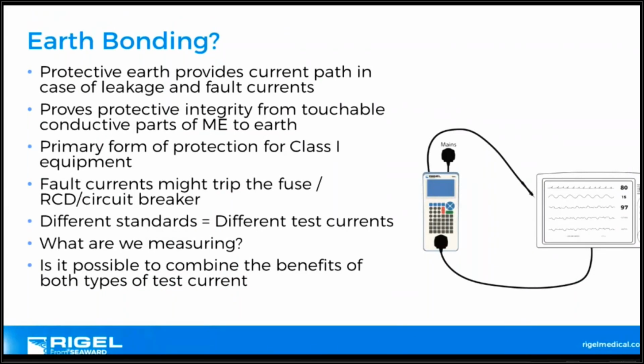So, as people would probably say, when we do earth bonding, protective earth is giving us that protective integrity from touchable parts. We've stressed that if the conductive part was to become live or hazardous, it's given us the primary form of protection for class 1 equipment. Then hopefully it will trip the fuse or the circuit breaker. But different standards have different currents and different pass-fail thresholds. But what are we measuring? We are measuring low resistance ohms.